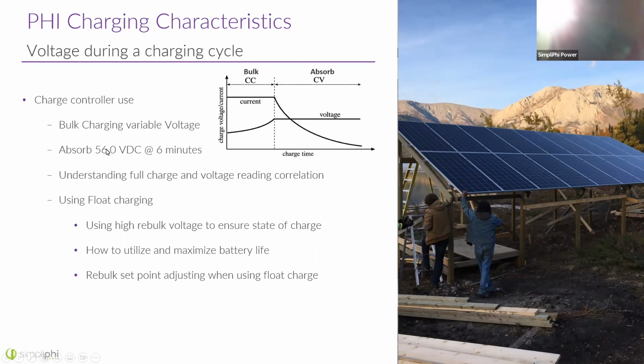This should say 56 volts for 6 minutes. Sorry about that mistake there on the screen. During that absorb cycle, it is going to maintain a constant voltage of 56 volts for 6 minutes, which is 1/10 of an hour. So that's the typical charging cycle.